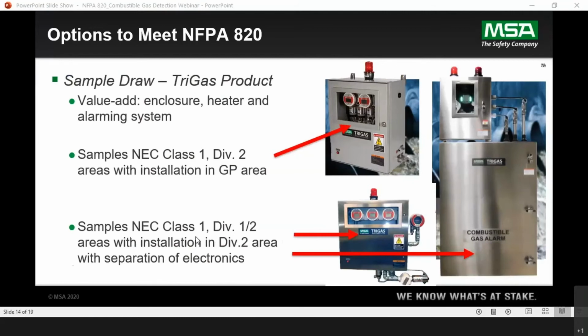Or if it gets more complex and you have a Division 1 sample, or need to place it in a Division 1 or Division 2 area, we have other designs. Here's one, for example, where we monitor the inside of the box with a sensor to be sure methane did not reach LEL levels. And if it does, we shut it off automatically with a power kill switch, if you will. And here's one where we separate the electronics entirely, so gas can flow here without any concerns. These are all XP components. And then this is our protected box that would house the exposed wiring.